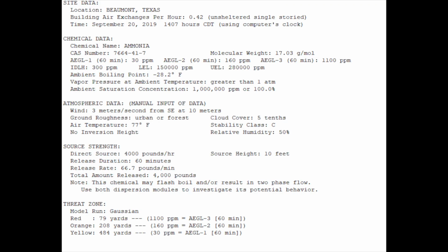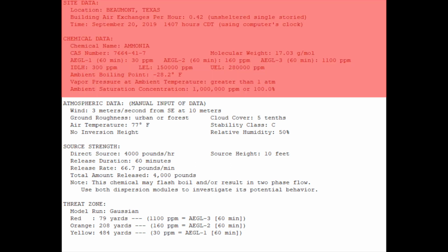Another thing we mentioned was dispersion analysis. Here's an example of a dispersion analysis case if you're wanting to evaluate the discharge of the PSVs and you want to know, is your community, is your personnel safe based on where we have this PSV routed. There's a bunch of different dispersion programs out there, like I mentioned earlier in this video. This is just ALOHA. It's a free version that's online. It has some limitations, but it's still used today for response personnel. What you're looking at right now is just the site data and inputs that I put in. We're running an ammonia release.